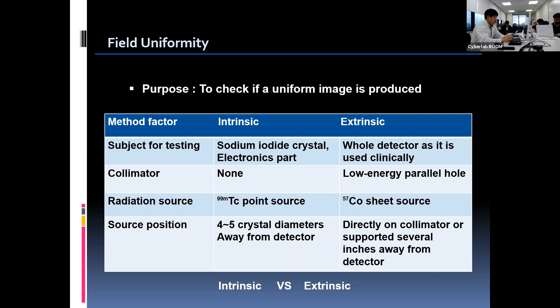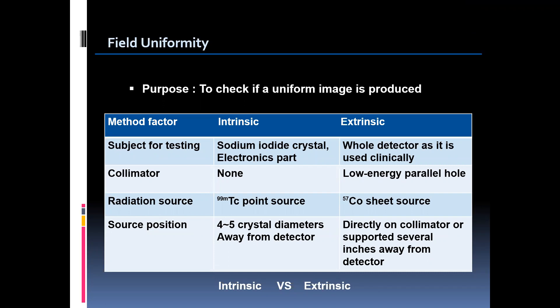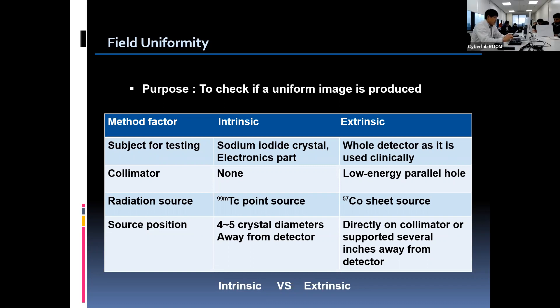This table is the comparison between intrinsic and extrinsic methods. Intrinsic testing is done without a collimator to check the condition of the sodium iodide crystal and electronic parts such as PM tubes. On the other hand, extrinsic is done with the collimator in place to assess the equipment as it is used clinically. We can choose one method or perform intrinsic testing weekly while doing extrinsic daily. Once a specific method is adopted, the same method should be used consistently for day-to-day comparison.